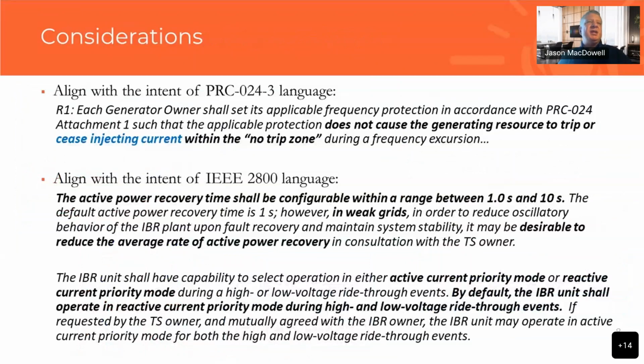There's some language called out specifically in the latest version of PRC 24. Requirement 1 says each generator owner shall set, as applicable, frequency protection in accordance with PRC 24 Attachment 1 so that it does not cause the generating resource to trip or cease injecting current within the no trip zone. I would love to hear comments, and please correct me if I got the intent of the FERC NOPR wrong. But if it is intended to prevent momentary cessation during the period when the voltage or the frequency is within the curves of PRC 24, the language of cease injecting current is probably more relevant than calling out active power to be maintained based on pre-fault levels.